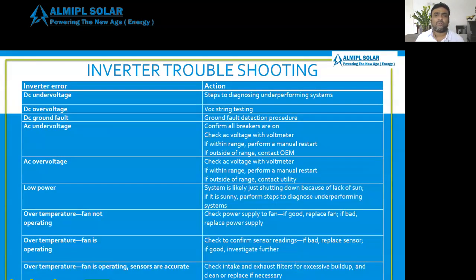DC under voltage: follow the steps to diagnose an underperforming system. DC over voltage: VOC string testing. DC ground fault: detection procedure. AC under voltage: confirm all breakers are on, check the voltage with a voltmeter. If within range, perform a manual restart. If outside of range, contact the operation and maintenance engineer. AC over voltage: check AC voltage with a voltmeter. If within range, perform a manual restart. If outside of the range, contact the utility.